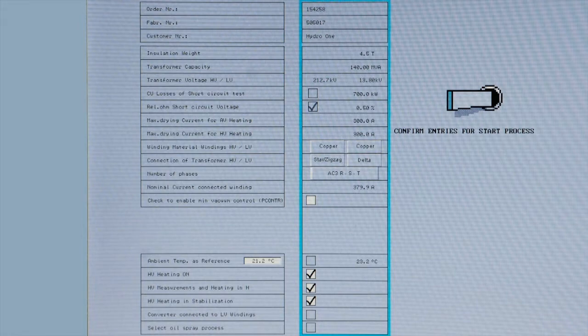Converter connected to LV windings. If the converter is connected to the LV winding, all data is entered as normal, but this box is checked, and the nominal current will be recalculated and all measurements will be correct. If not, the HV data has to be taken from the LV and so on, and the LV and HV data will be switched. When connected to the LV winding, the HV winding has to be short-circuited.